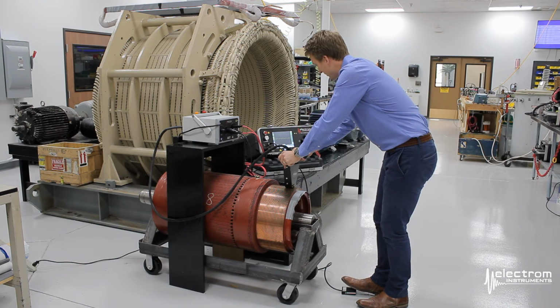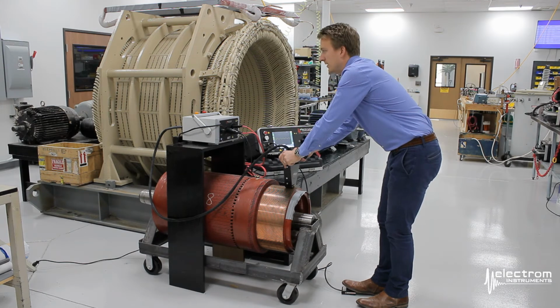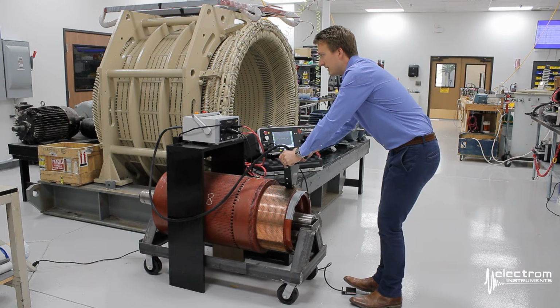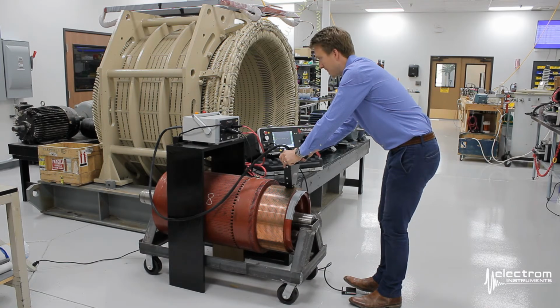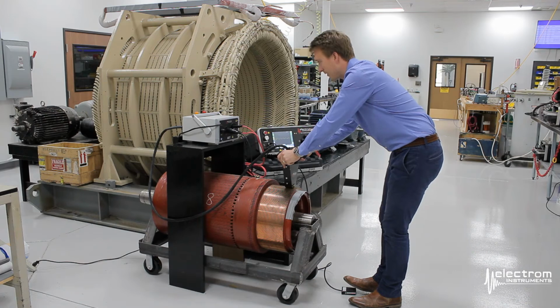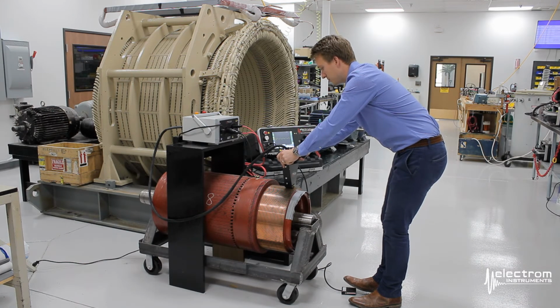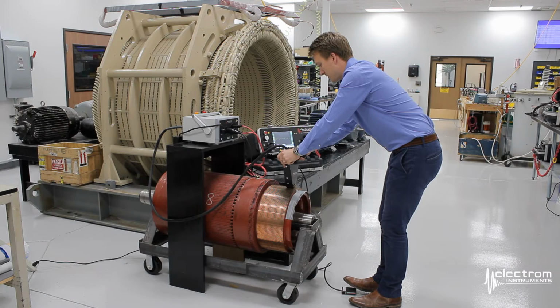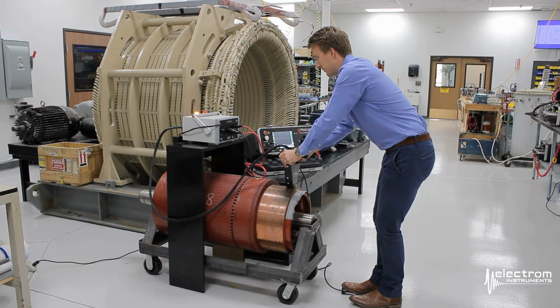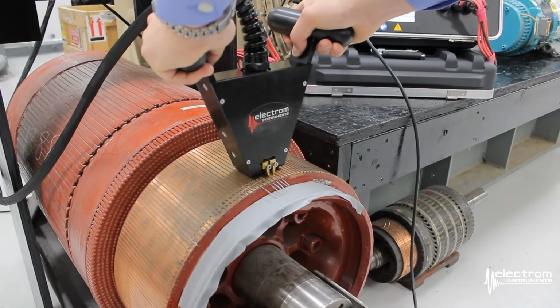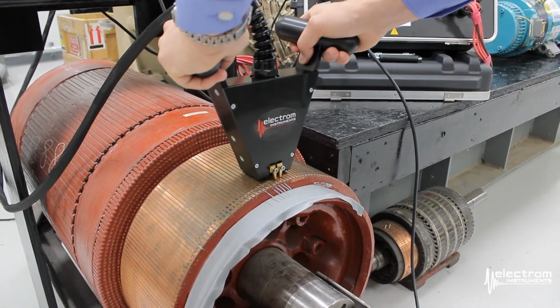This time it will be very fast. It has all the settings, it knows what to do. So step on it, it's done. The orange or yellow light indicates that high voltage is on. If the red light turns on, that means the test has failed. When both lights are off, we are okay to move to the next bar. Okay, 1 bar over. Test, we're okay. Another bar. Test.